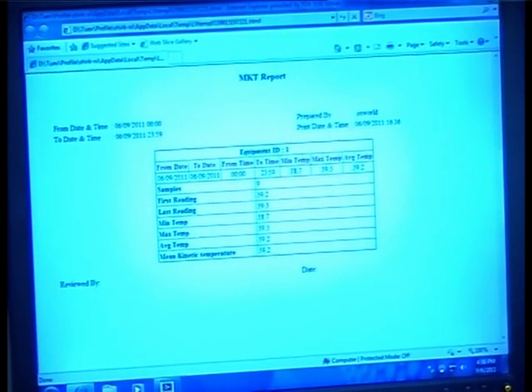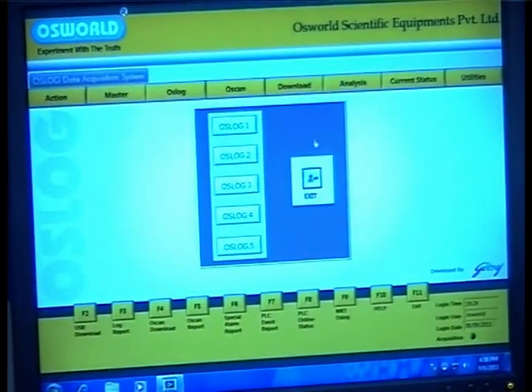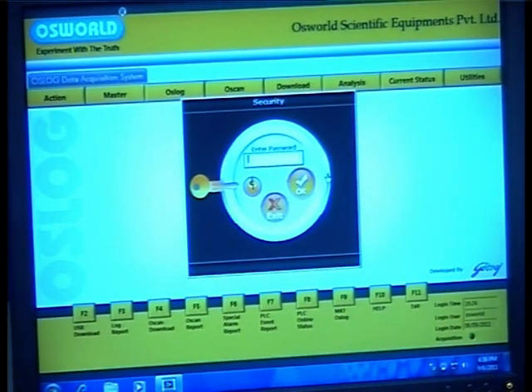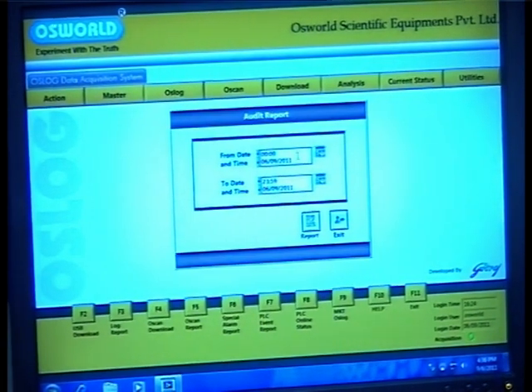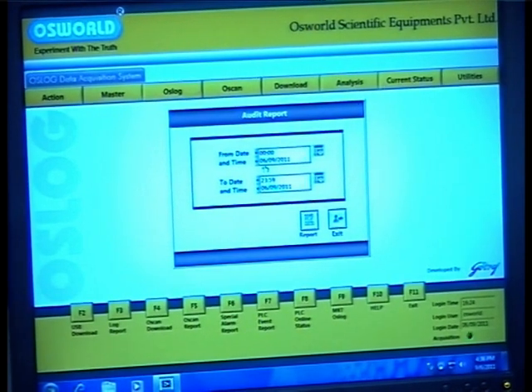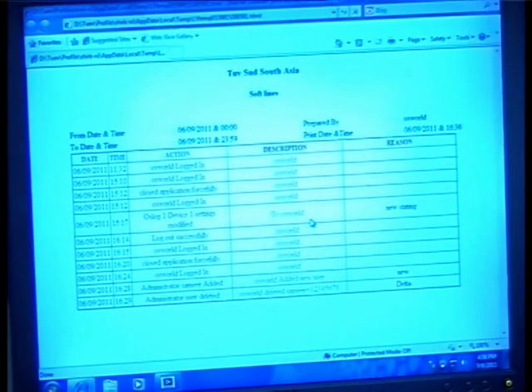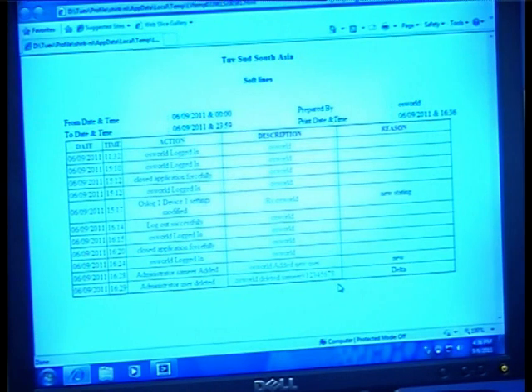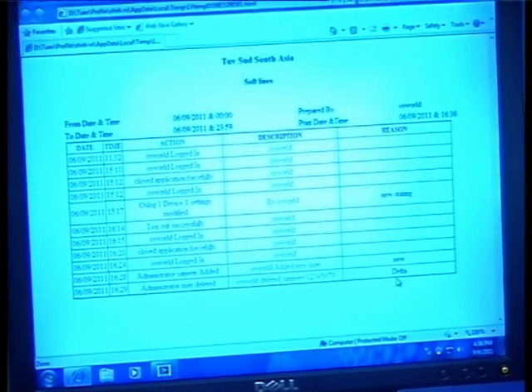To generate the audit trail report, click on the same analysis drop-down used for the MKT report, select the audit report option, and enter your password. Enter the days that you would like to view the report for and click on report. The report is generated and, as you can see, the details of all modifications and changes made are visible along with the date, the time, and the reason for each.